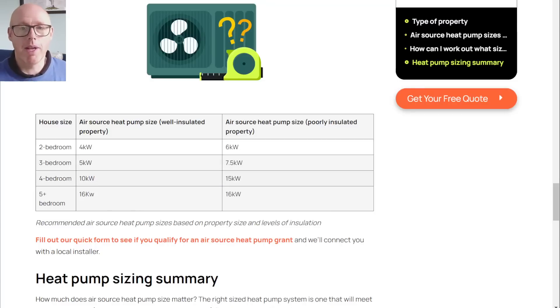My house is a 4-bedroom, 140 square metre detached house built in 1996. No blown bead cavity wall insulation or super-duper upgrades. We do have double glazing and I've topped up the loft insulation — very cheap and easy. We've also got a big extension out the back; I've put an insulated roof on but it's still got masses of glazing on three sides. My heat loss for this nearly 30-year-old house is 5.8kW calculated using the forms or using Heatpunk — it comes out pretty much the same. I had two professional heat loss surveys and did my own DIY one using two different methods. Always came out in that kind of ballpark.